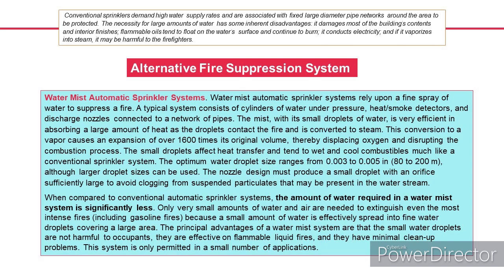These are the following. First is the water mist automatic sprinkler systems. Water mist automatic sprinkler systems rely upon a fine spray of water to suppress a fire. A typical system consists of cylinders of water under pressure, heat/smoke detectors, and discharge nozzles connected to a network of pipes. The mist, with its small droplets of water, is very efficient in absorbing a large amount of heat as the droplets contact the fire and are converted to steam. This conversion to a vapor causes an expansion of over 1,600 times its original volume, thereby displacing oxygen and disrupting the combustion process. The small droplets affect heat transfer and tend to wet and cool combustibles much like a conventional sprinkler system. The optimum water droplet size ranges from 0.003 to 0.005 inches, 80 to 200 microns, although larger droplet sizes can be used. The nozzle design must produce a small droplet with an orifice sufficiently large to avoid clogging from suspended particulates that may be present in the water stream.